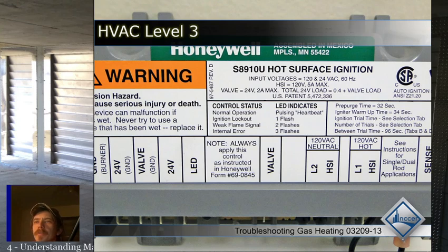If you're trying to troubleshoot a thermostat, alright, and it's not operating properly, you can jump the terminals, okay? Old thermostats used to have what they call a sub base. I guess technically you still have a sub base on thermostats where you connect the wires together. Yeah, you could still call it a sub base. I don't think about it as a sub base. I think about the old Honeywell thermostats as having a sub base, but you still have a base for the thermostat where all your wires connect before you put it on the wall, right?